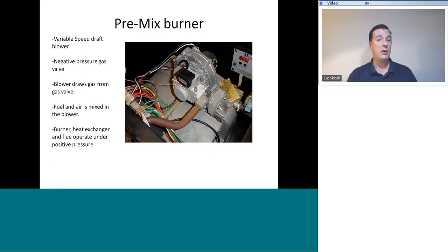And the combustion blower blows into the burner and into the heat exchanger, with the gas supply going through the gas valve, and the discharge of the gas valve is on the suction side of the blower. These gas valves actually operate under negative pressure. All of the other gas valves that we've looked at before operate under positive pressure and force gas into the burner. This gas valve operates under negative pressure. What? Well, sure, there's positive pressure in the gas line leading into the valve, but on the outlet of the valve, it is controlled by the suction of the fan. So the harder the fan sucks on the gas valve, the more gas it sucks through the gas valve. So the gas valve is always operating under a suction from the combustion fan.